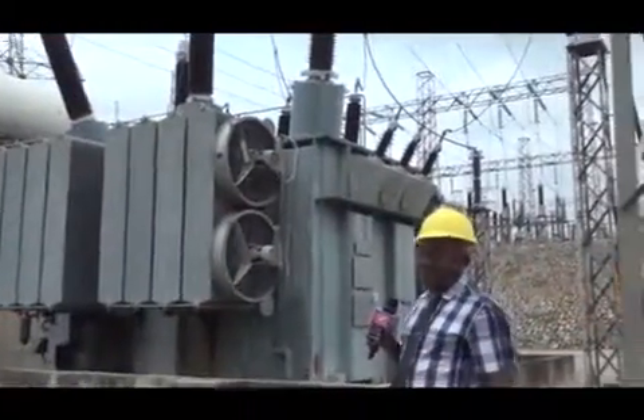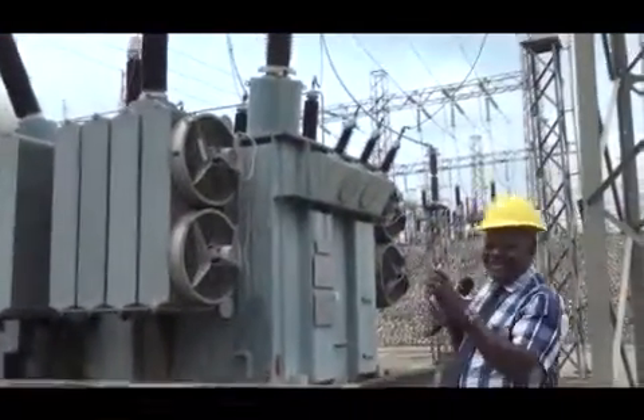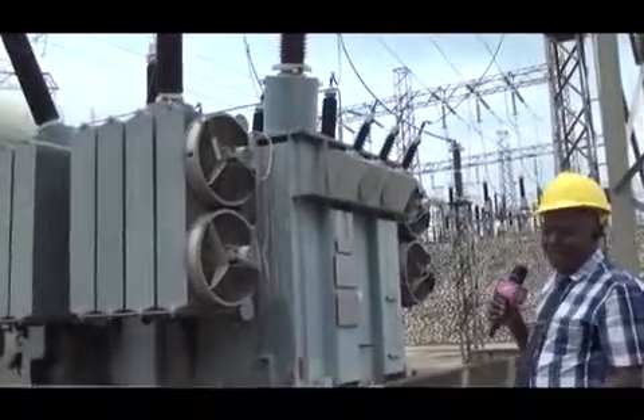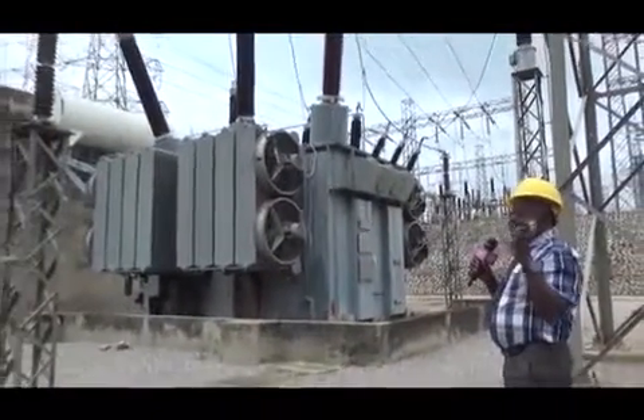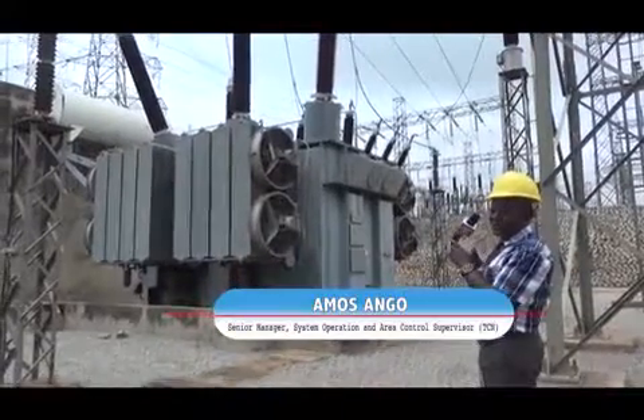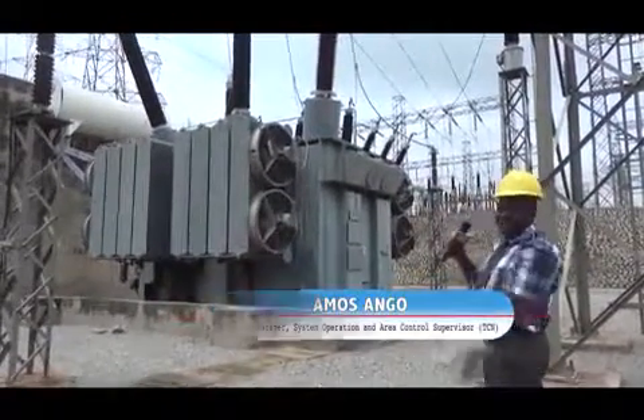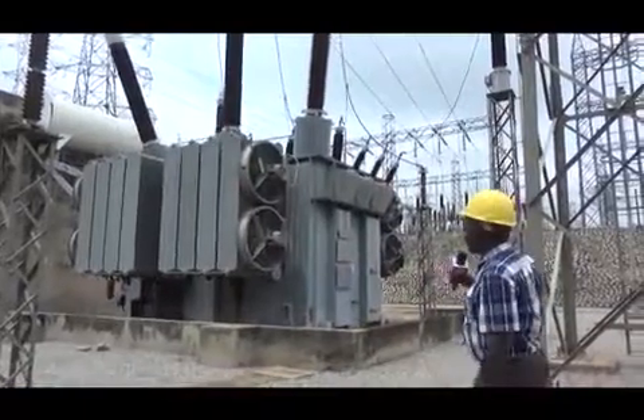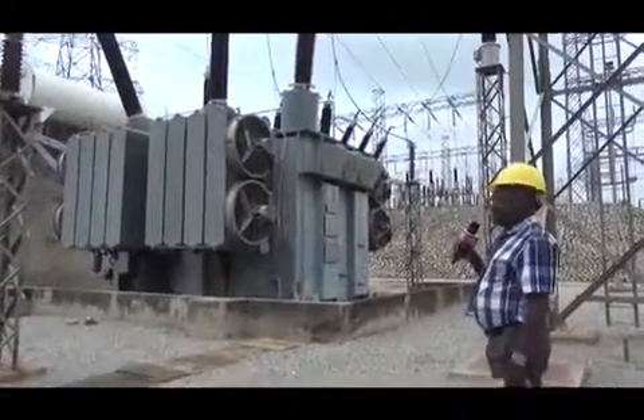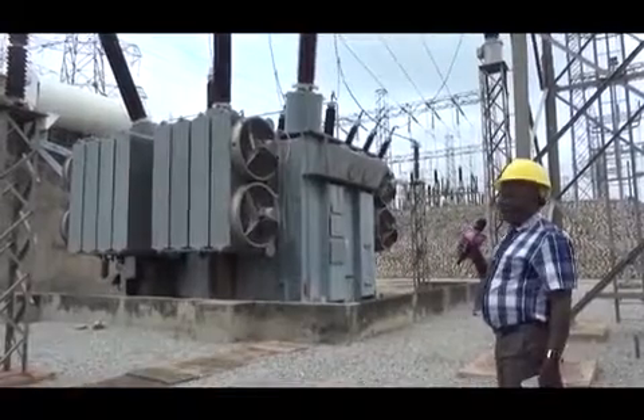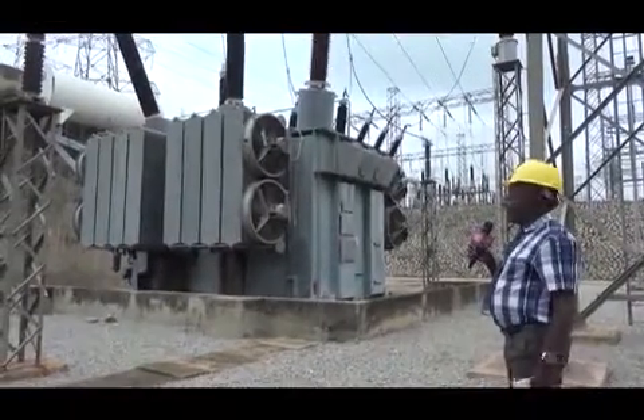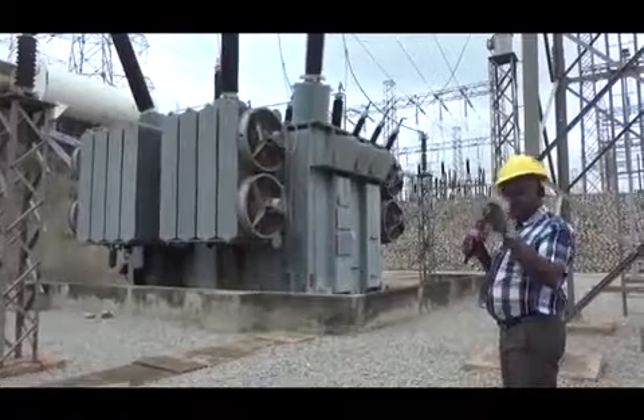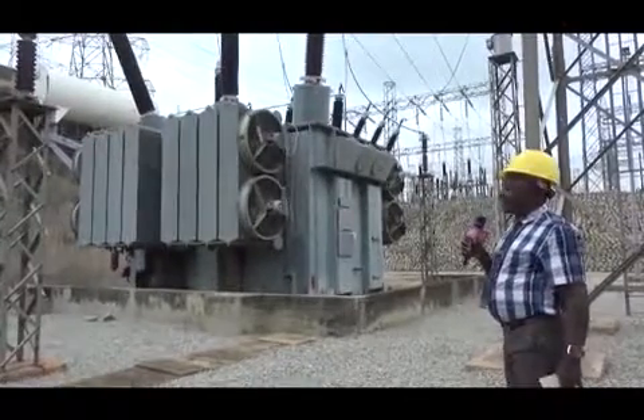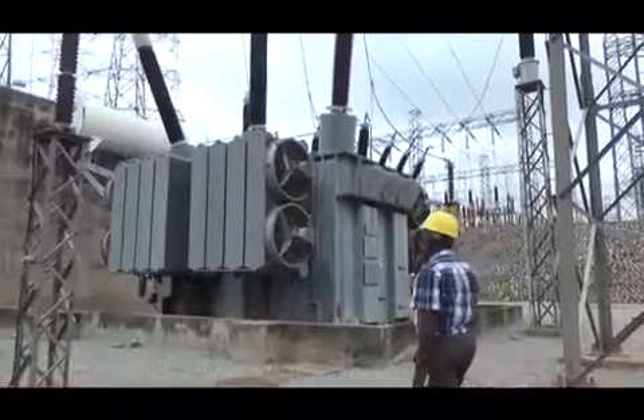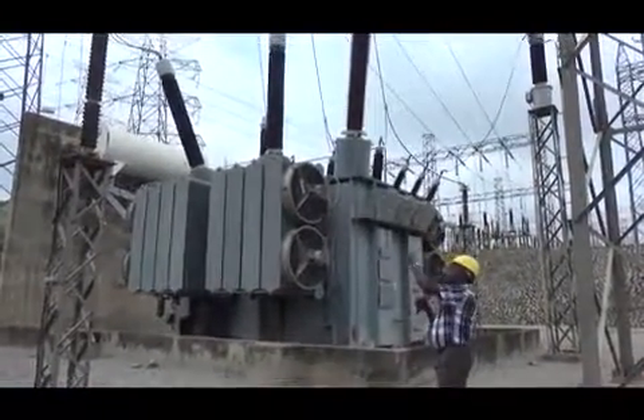At the transformer section, he said, this is where the 330 kV voltage terminated. The voltage we are receiving from Shiroro goes into this transformer and is not coming out the same again. And this transformer, the rating is 150 MVA, and the voltage level is 330 kV/132 kV. So that's the level here. You can see now, all these things you see are protective devices. This is what we call the lightning arrestor.